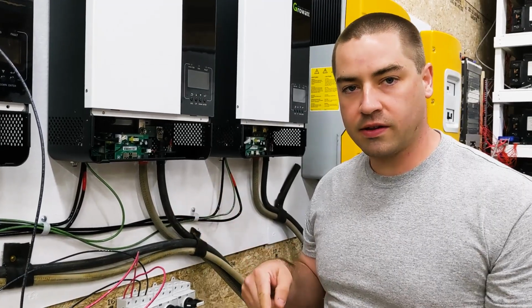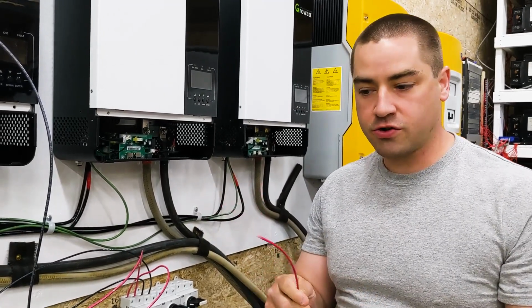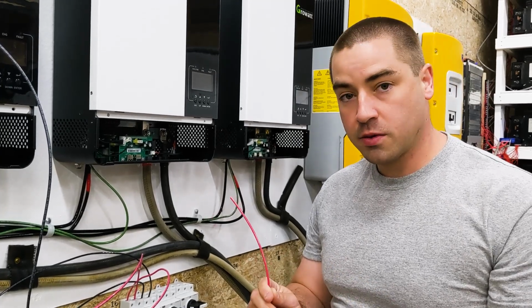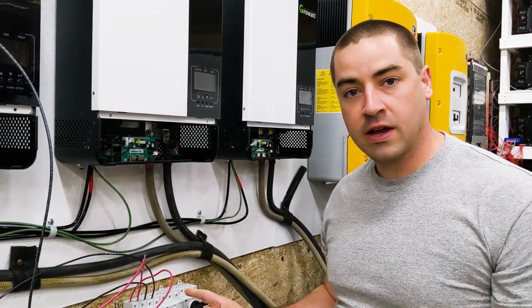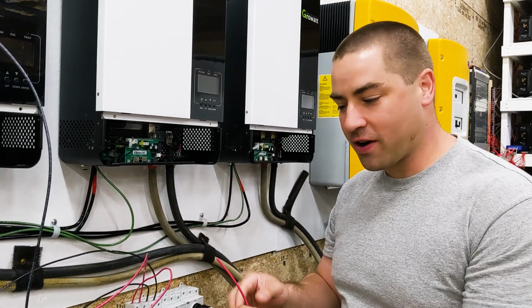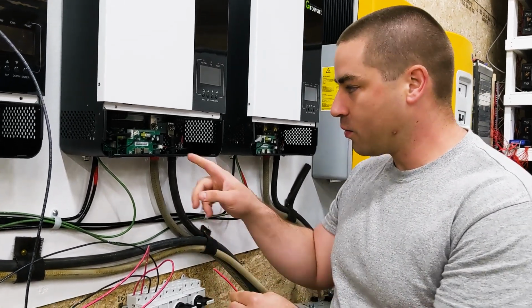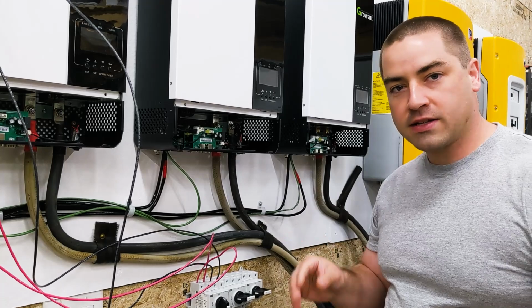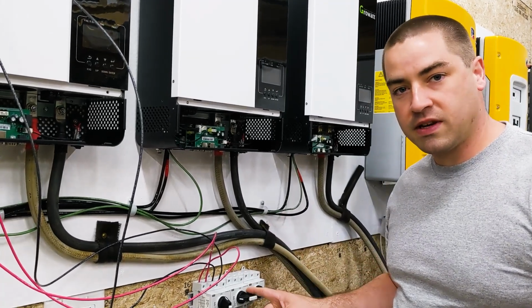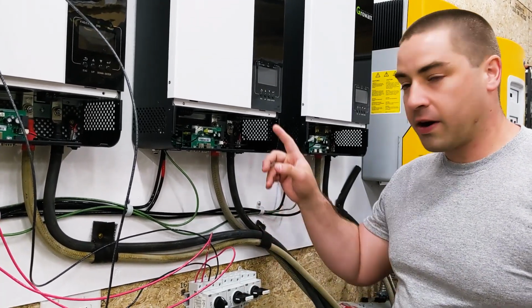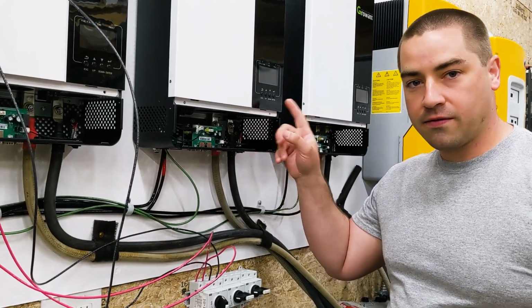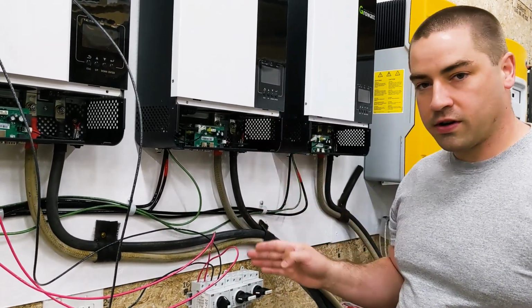From the solar array to here, I'm using 12 gauge stranded THHN wire, so I'm just going to continue this off of these PV disconnects. I have 2 positives and 2 negatives coming to this PV disconnect from the solar array, but I only have 1 positive and 1 negative on the inverter for each one.